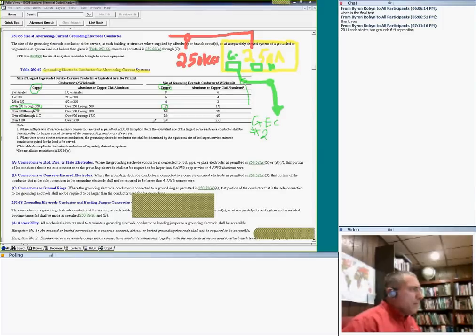Any question, guys, about how to use this table? You size it based on the service entrance conductors coming to the building. Any question, my friends? So let's go size the system bonding jumper. It's called the main bonding jumper, as a matter of fact. We size it the same way. We come here, go all the way up to here, and in this case my bonding jumper will be number 2. The only difference between the bonding jumper and the grounding electrode conductor is that if you go higher than this number, there's a different calculation: you take 12.5% times the conductor size.